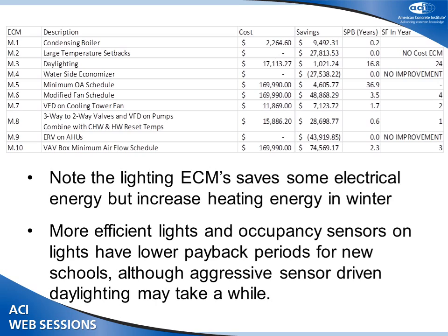We can at least guide the designers to look at these sorts of things first. The lower the payback, the more likely I'm going to get a return on my investment. As I said earlier, the more efficient lights and occupancy sensors on the lights have lower payback periods in new schools. Although aggressive sensor-driven daylighting, if you look down in here, may take a while.